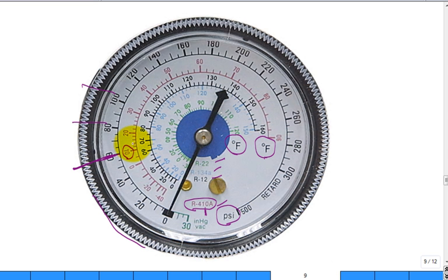So that's what they're doing, you move up, you move there. So what they can do is they can diagnose what the temperature of the refrigerant is in that evaporator or in the condenser because of the pressure at which it's evaporating or condensing. And often it's out of whack because it's either overcharged or undercharged. Often undercharged. There's a slight leak in the system. All right. Or sometimes there'll be a blockage in the system. Then the pressure will be out of whack because of that.